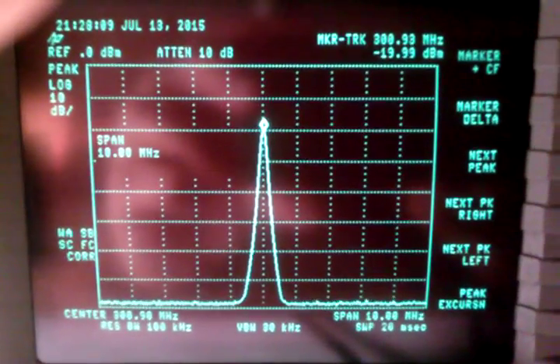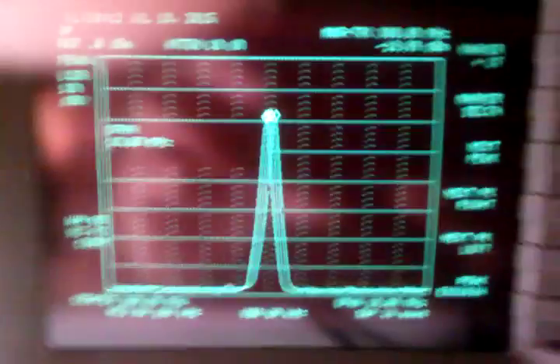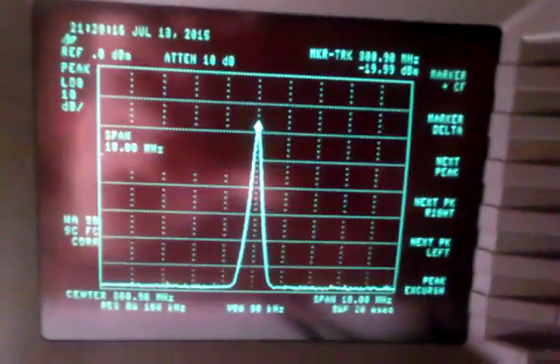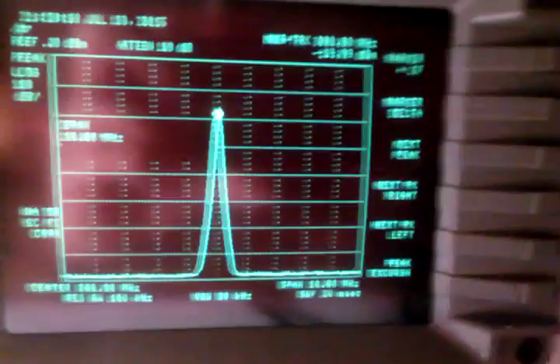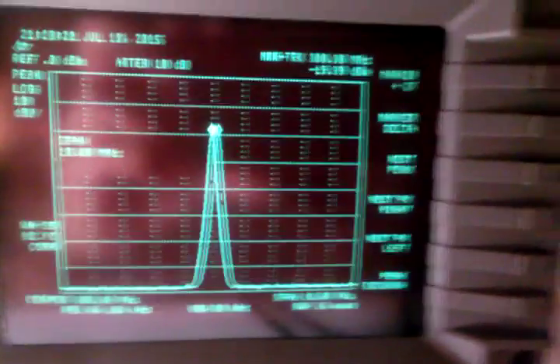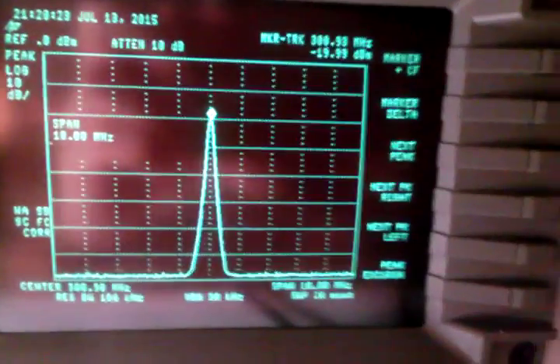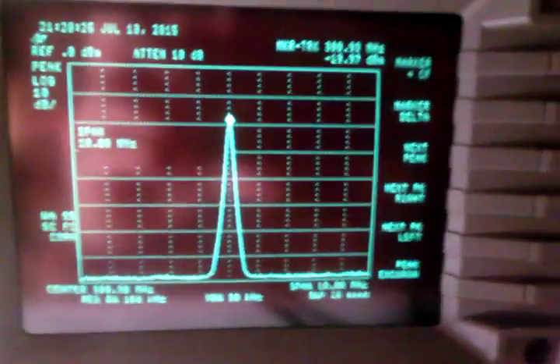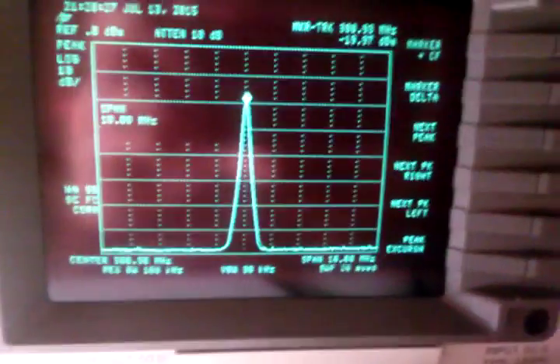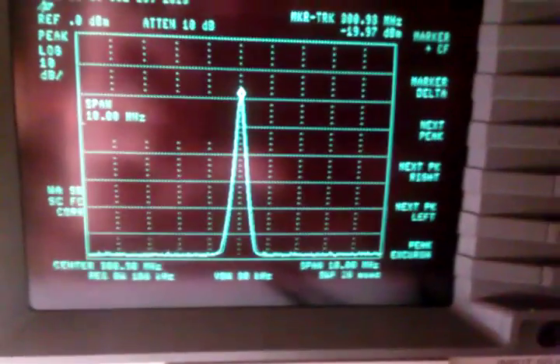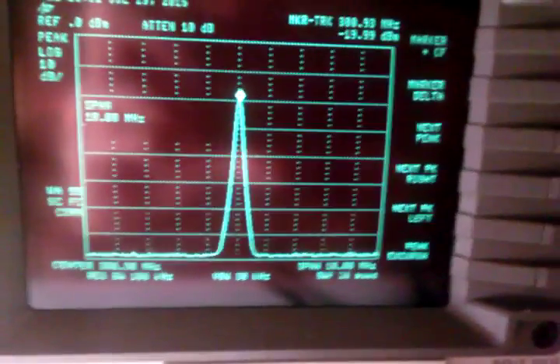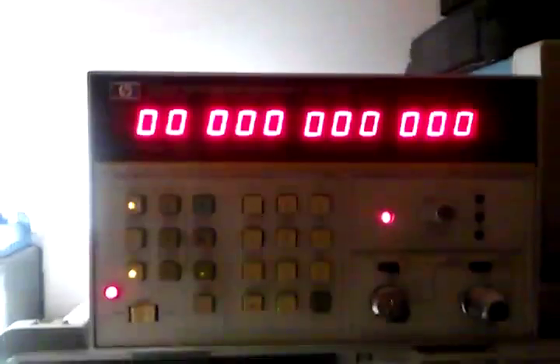As far as the frequency is concerned, we're off about 900 kilohertz, which is a lot. But remember, this instrument, the accuracy is supposed to be plus or minus 5 megahertz. So we are well within spec for this instrument. With the counterlock board, it would be far more accurate. So it is fixed, and that pretty much concludes this video. And by the way, this is my new frequency counter, and it's working as well.